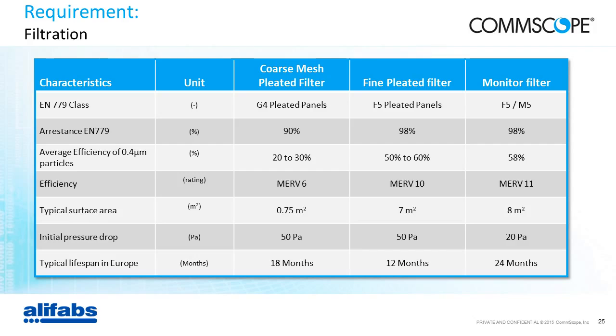So what it provides you is both criticality. You can use it on critical sites. You have higher airflow, so that means you can use it on highly loaded sites. And you don't have to maintain it too much, actually. Typically, up to 24 months. But we've seen in some environments that you can run the system for 3 or 4 years without any maintenance whatsoever, with no drop whatsoever in the performance of the system.